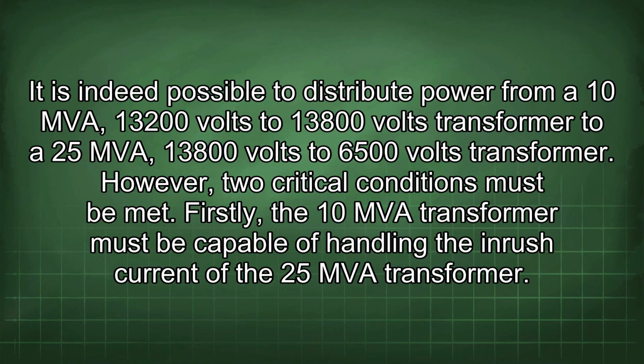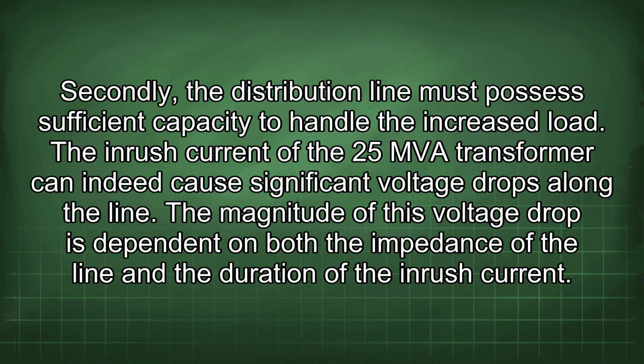It is indeed possible to distribute power from a 10 MVA 13,200 volts to 13,800 volts transformer to a 25 MVA 13,800 volts to 6,500 volts transformer. However, two critical conditions must be met. Firstly, the 10 MVA transformer must be capable of handling the inrush current of the 25 MVA transformer. Secondly, the distribution line must possess sufficient capacity to handle the increased load.